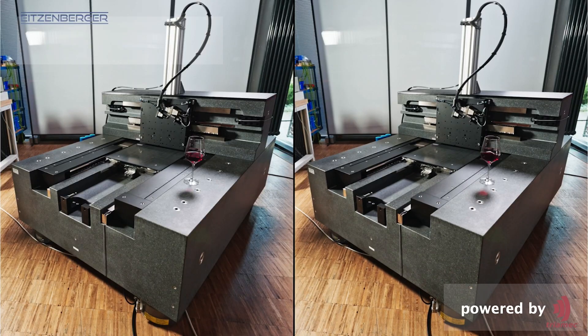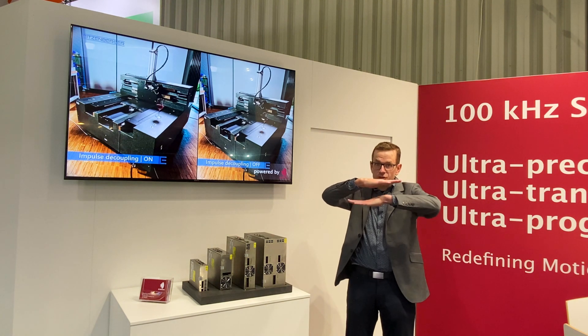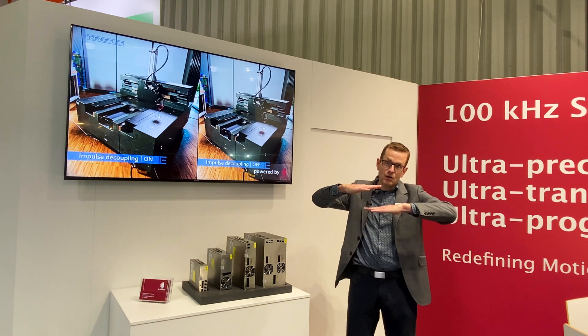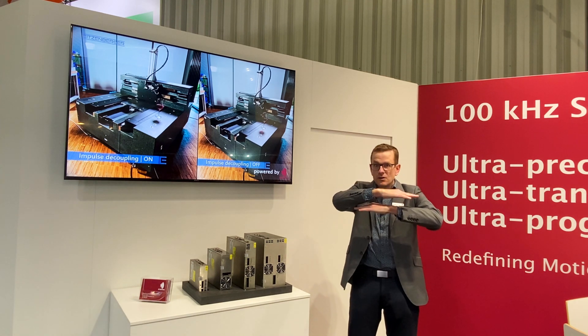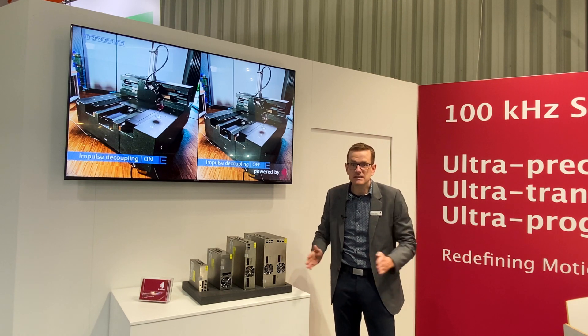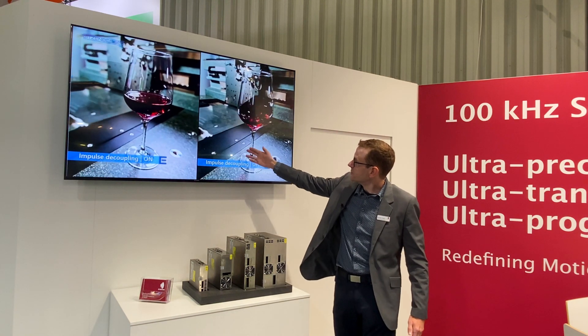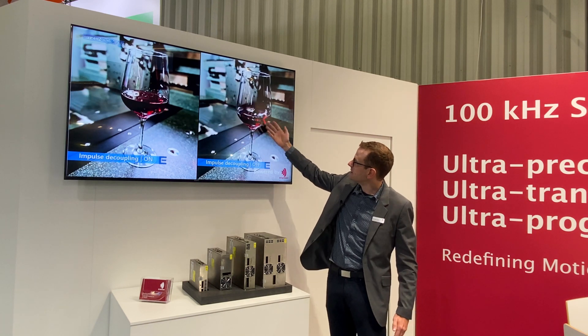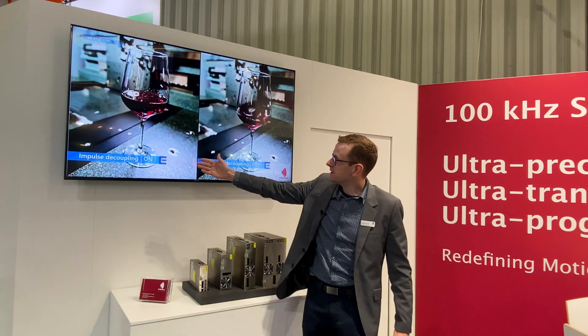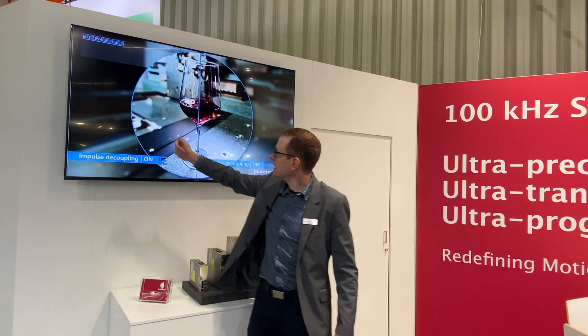Here we show an example for impulse decoupling. This means the stator of the linear motor is not fixed but movable, and also controlled by a servo axis. With this, the impulse of the movement of the axis is not transferred to the base and does not generate excitation of the base. Here we see the machine with a fixed stator — you see no movement of the stator, and in this case we have a huge excitation of the base. In contrast, with impulse decoupling the stator is moving and we have nearly no excitation of the base.